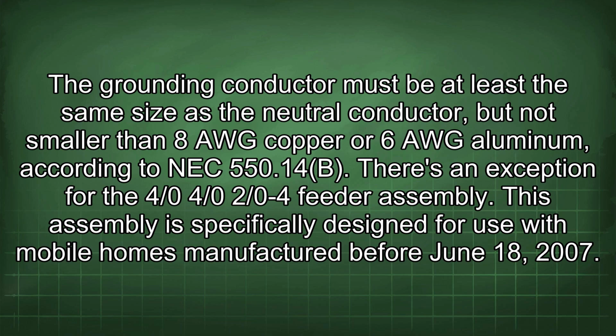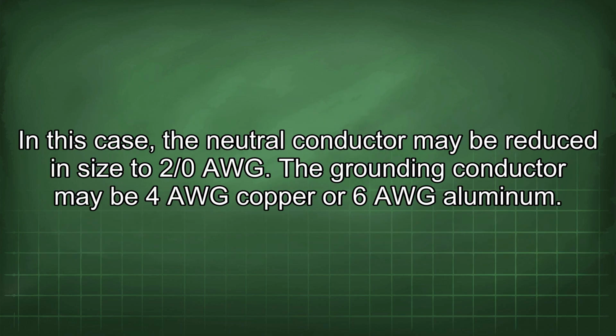550.14b. There's an exception for the 4/0-4/0-2/0-4 feeder assembly. This assembly is specifically designed for use with mobile homes manufactured before June 18, 2007. In this case, the neutral conductor may be reduced in size to 2/0 AWG. The grounding conductor may be 4 AWG copper or 6 AWG aluminum.